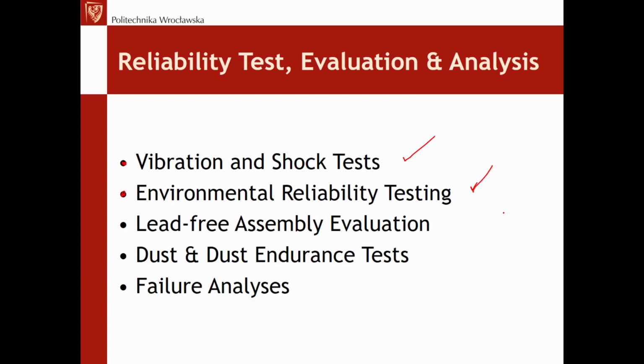So this is usually done in special climatic chambers. For the environmental testing, the devices are put under the stress of various temperatures and various humidity, sometimes various pressures. So it really depends what we are testing and what needs to be checked in our device, because of course it's going to be different if our device is to work in free space, so be part of some satellite, or if our device is to be part of a submarine or whatever. So the environmental reliability test is a really important kind of testing in the reliability group.